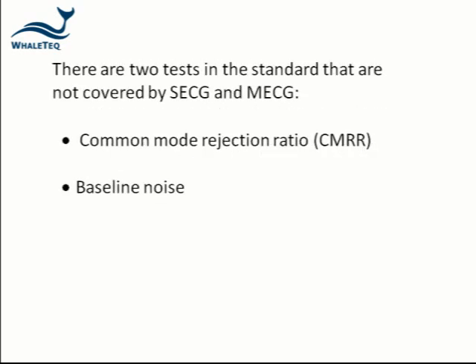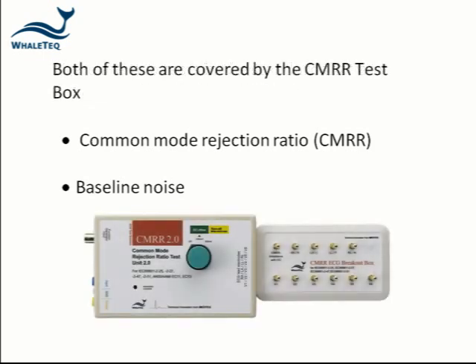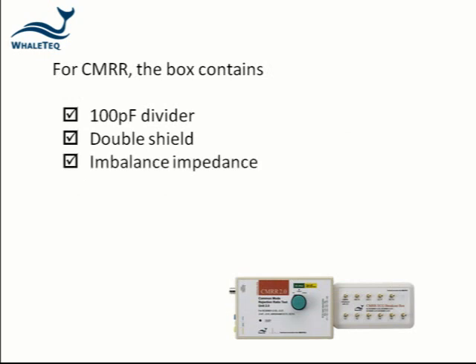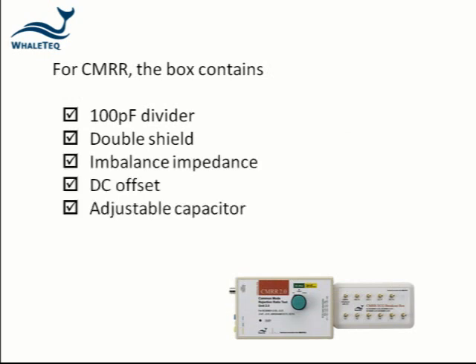There are two tests in the ECG standards that cannot be performed with the SECG or the MECG. These are the Common Mode Rejection Ratio, or CMRR test, and the baseline noise test. For these tests, the CMRR test box should be used. For CMRR, the box contains the 100 pF divider, double shield, imbalance impedance, DC offset, and adjustable capacitor as required by the standard.